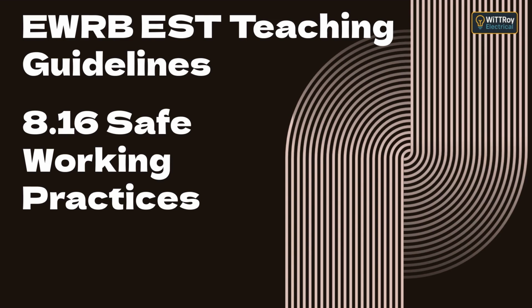Topic E, Live Work and Approach Boundaries. Now for Topic E, Live Work and Approach Boundaries. Working live is extremely dangerous and should only occur when absolutely necessary, such as testing, fault finding, or commissioning, where isolation isn't possible. Under AS/NZS 4836 Clause 3.3, live work must be justified by risk assessment, approved by a competent person, and controlled using insulated tools, barriers, and PPE. There are also approach boundaries that specify how close you can get to exposed live parts. Even at 230 volts, you must keep uninsulated body parts and conductive tools away from live conductors unless you are trained and authorized. If live testing is required, keep one hand behind your back, stand on an insulated mat, and avoid contact with earthed metal surfaces.